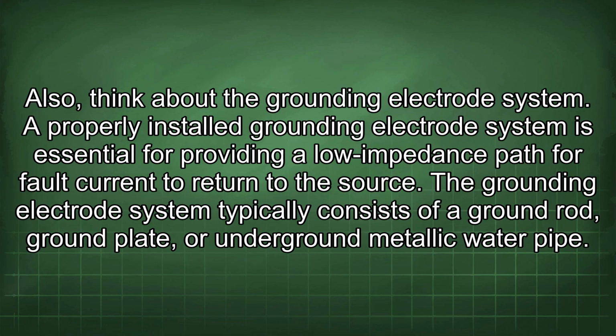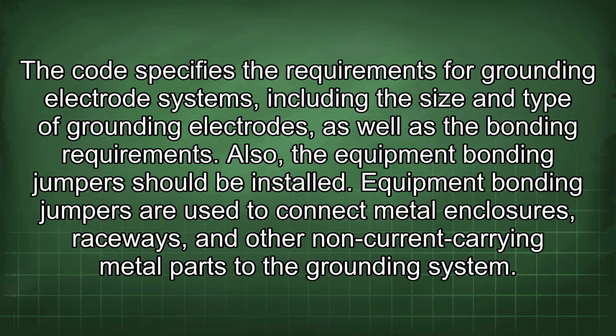Also, think about the grounding electrode system. A properly installed grounding electrode system is essential for providing a low impedance path for fault current to return to the source. The grounding electrode system typically consists of a ground rod, ground plate, or underground metallic water pipe. The code specifies the requirements for grounding electrode systems, including the size and type of grounding electrodes, as well as the bonding requirements. Also, the equipment bonding jumpers should be installed.